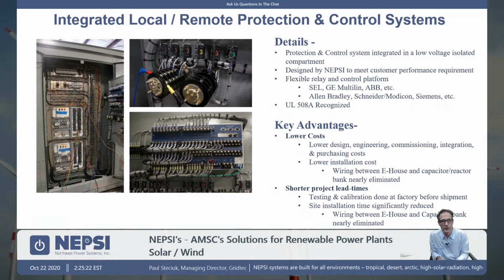Well, if you specify that the control and protection system is part of the metal enclosed system, it means that we're installing all those relays into our equipment. We're testing before it leaves our factory. We're setting them before it leaves our factory. It means that it shows up to your site ready to go.